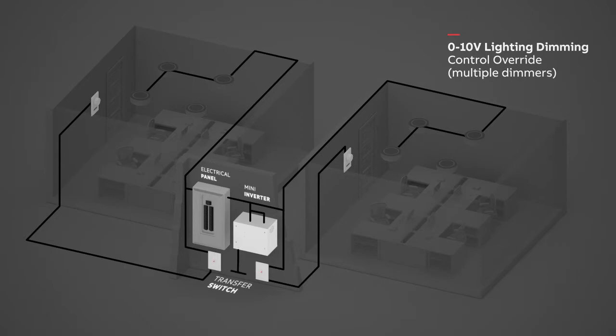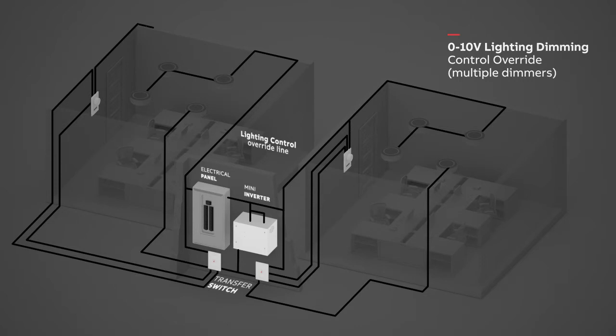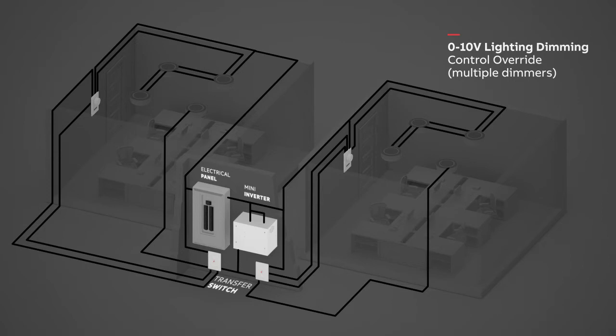Wire the mini inverter to all transfer switches and connect each transfer switch to the lights that will be used as emergency lighting. Wire the lighting control override line to connect each transfer switch to the dimmer switch and to all the lights controlled by the dimmer switch in each room, including the emergency light.